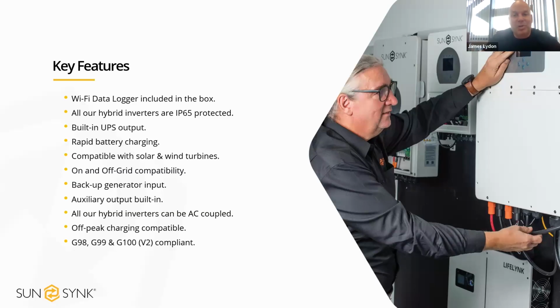And that output is turned on, which it can be set by the installer or the user, but it all works around the battery SOC. So typically someone might say, right, when the battery's at 100%, let's turn that on, but let's turn it off when the battery's at 95%. So the fundamentals are similar to your eddies and your iBoosts. Like I say, they will start diverting at like 200 watts, and the immersion will take that. But for efficiency, the immersion wants what it wants. It wants 3 kilowatt. So that's why we give it the full requested power.